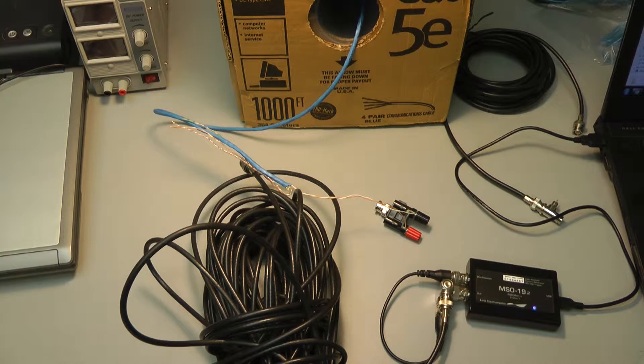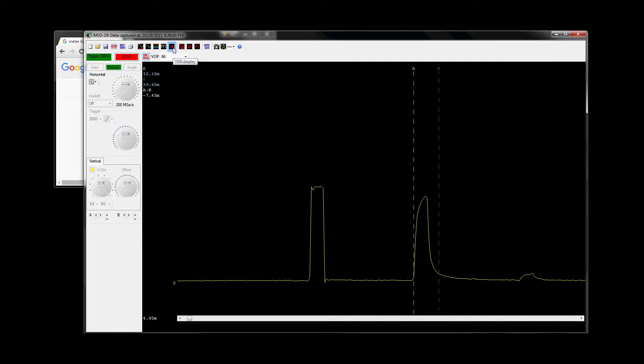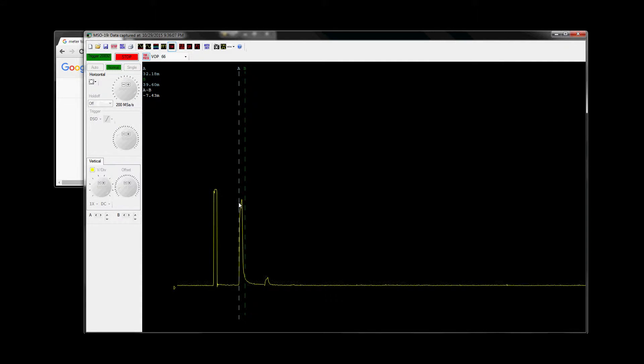So let's go to the TDR function. To enter it, you just click the TDR button and let's zoom out a bit — this is what it looks like. You also need to set the velocity factor. The velocity factor for the Belden cable is 66, as specified in their datasheet.